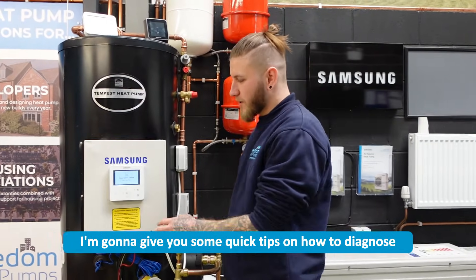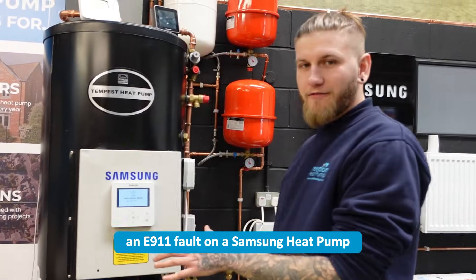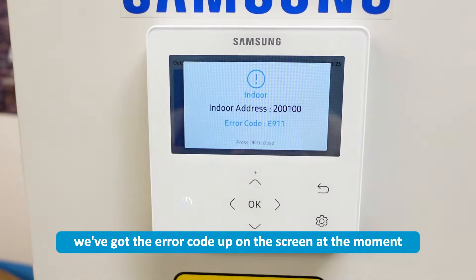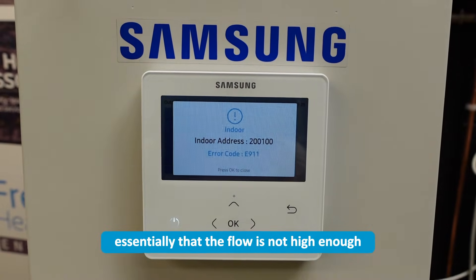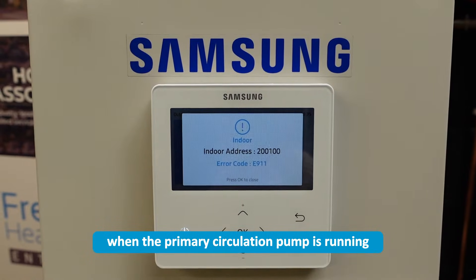Today I'm going to give you some quick tips on how to diagnose and potentially resolve an E911 fault on a Samsung heat pump. As you can see here, we've got the error code up on the screen at the moment. E911 essentially means that the flow is not high enough when the primary circulation pump is running.